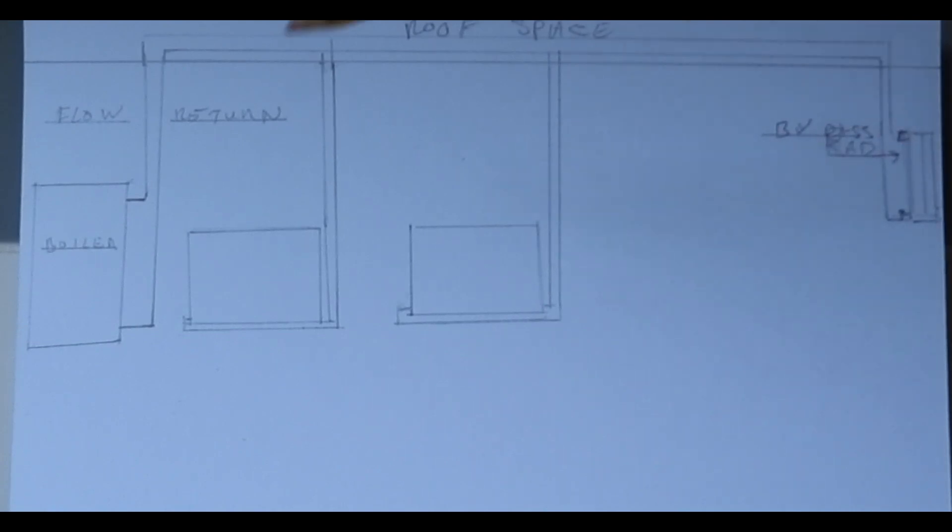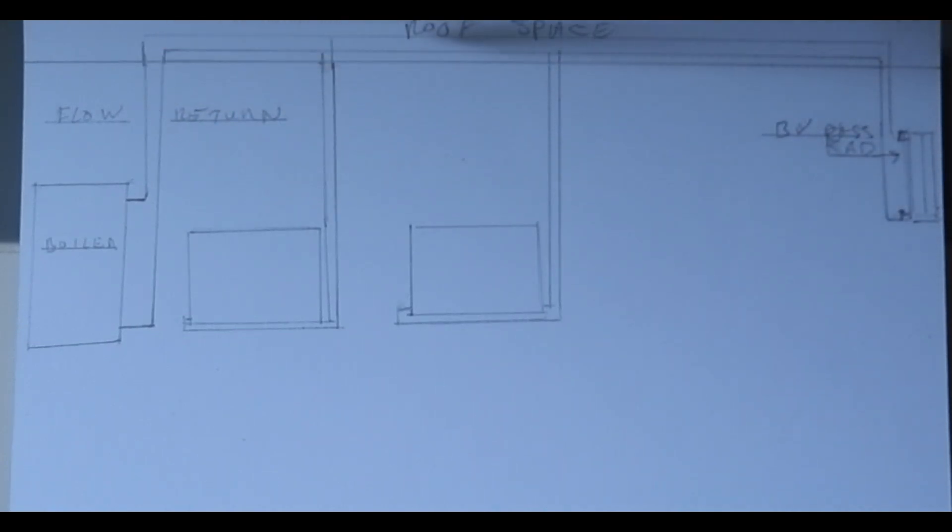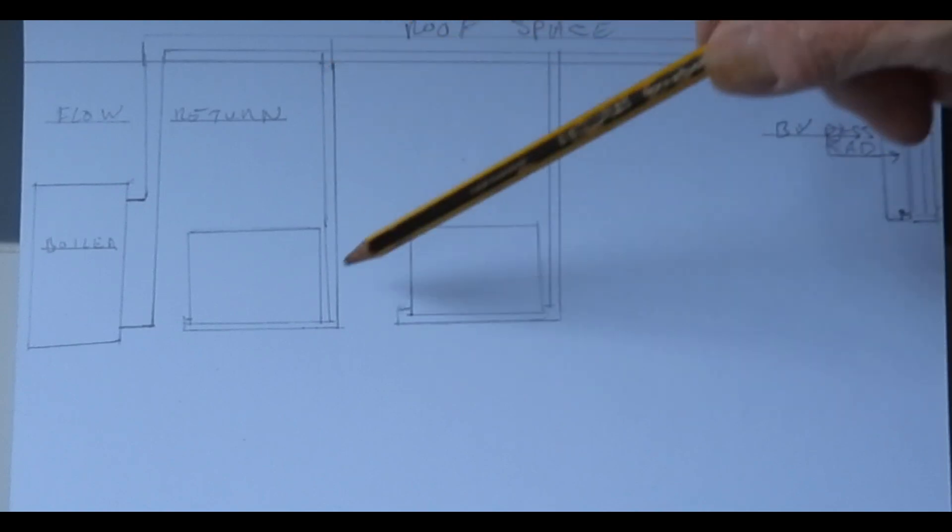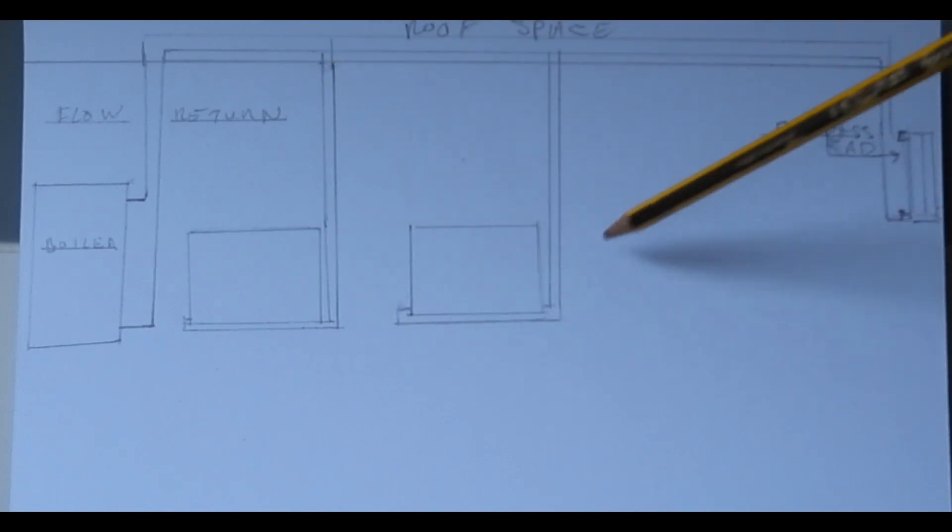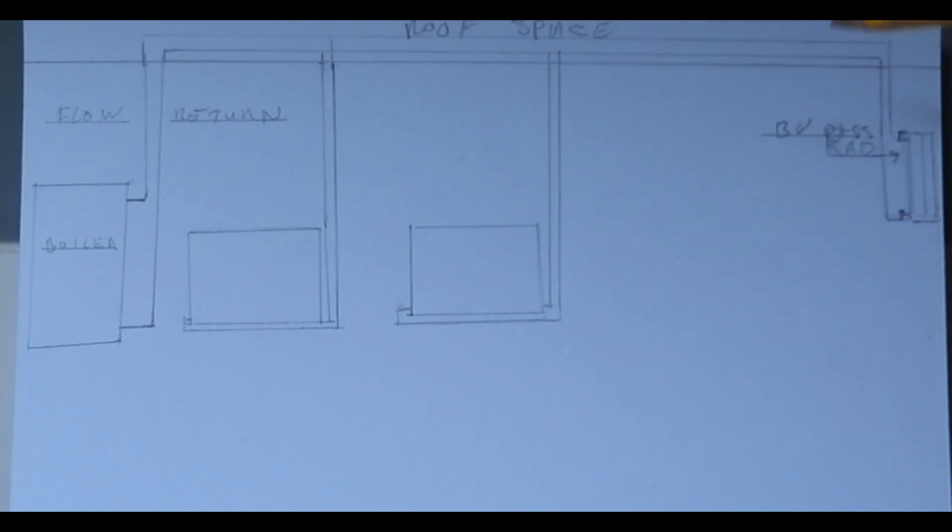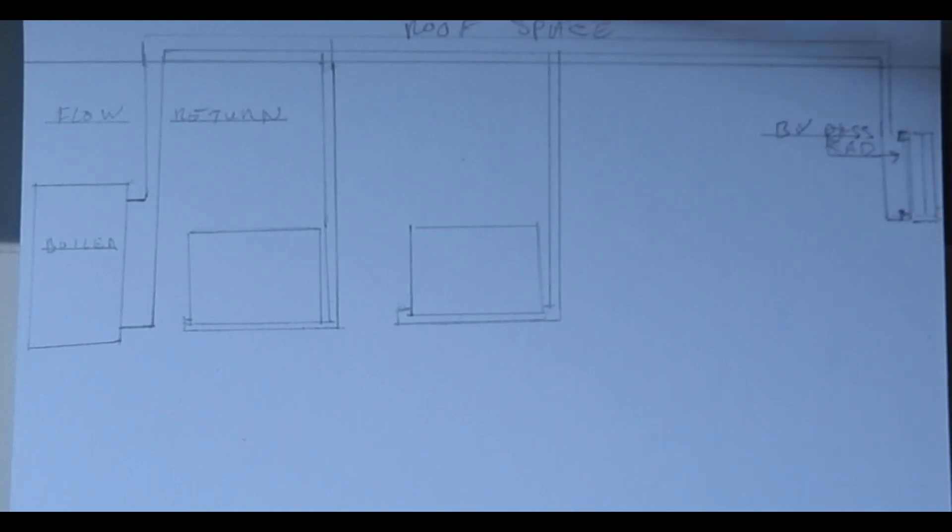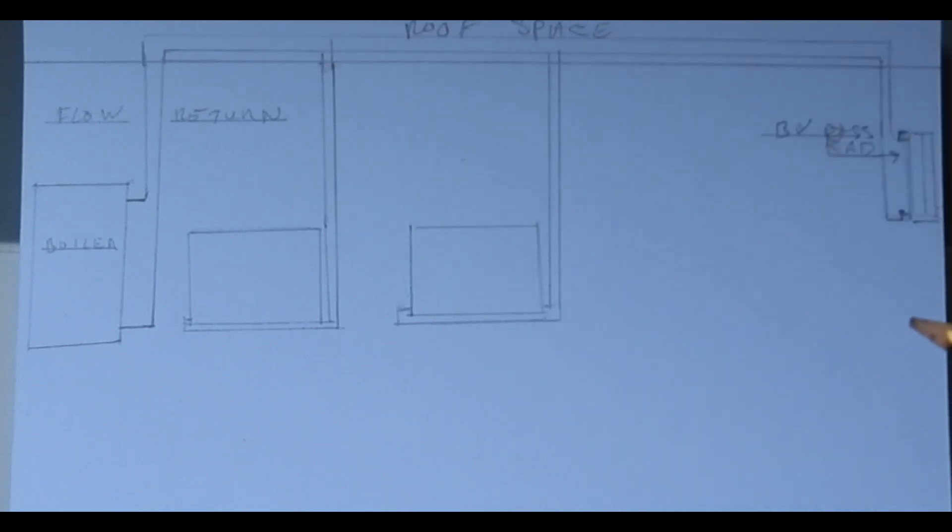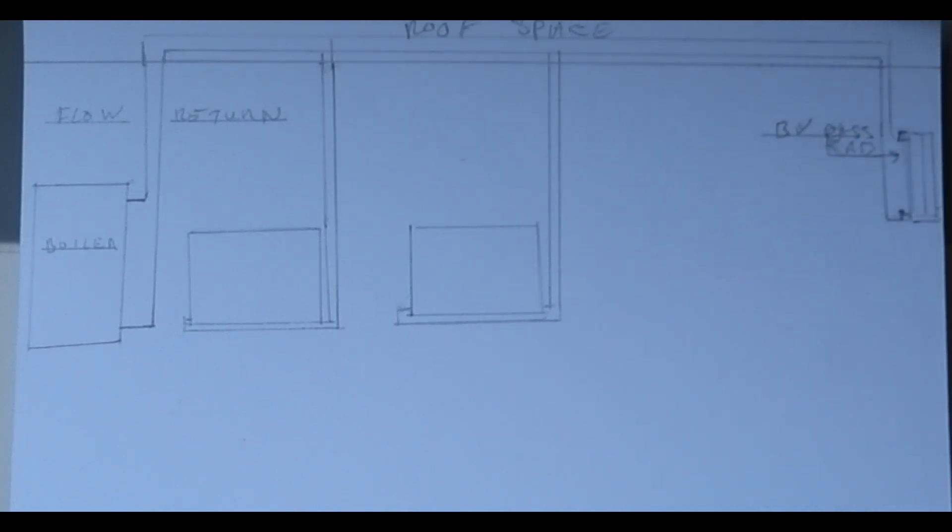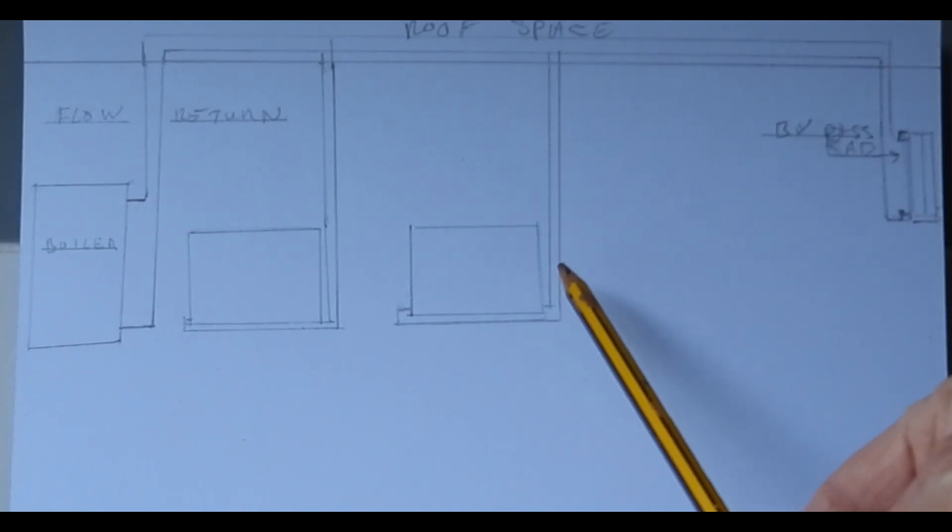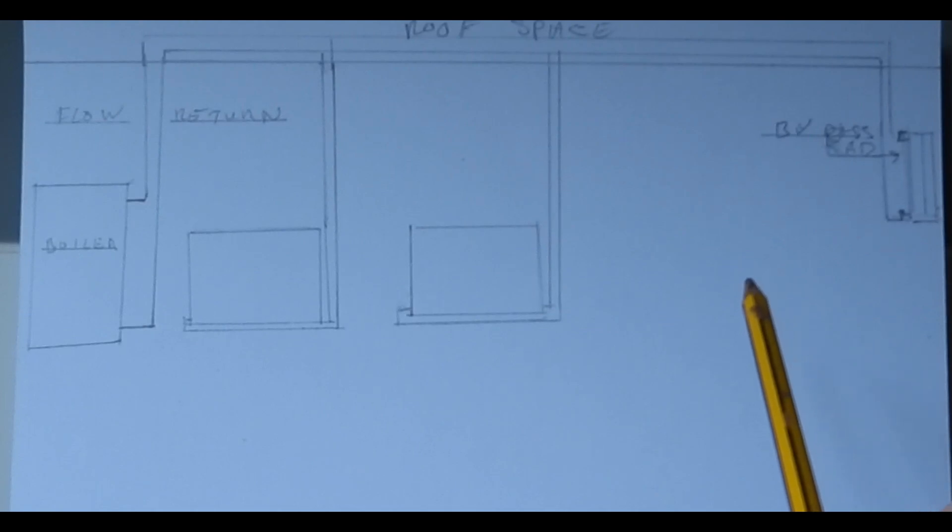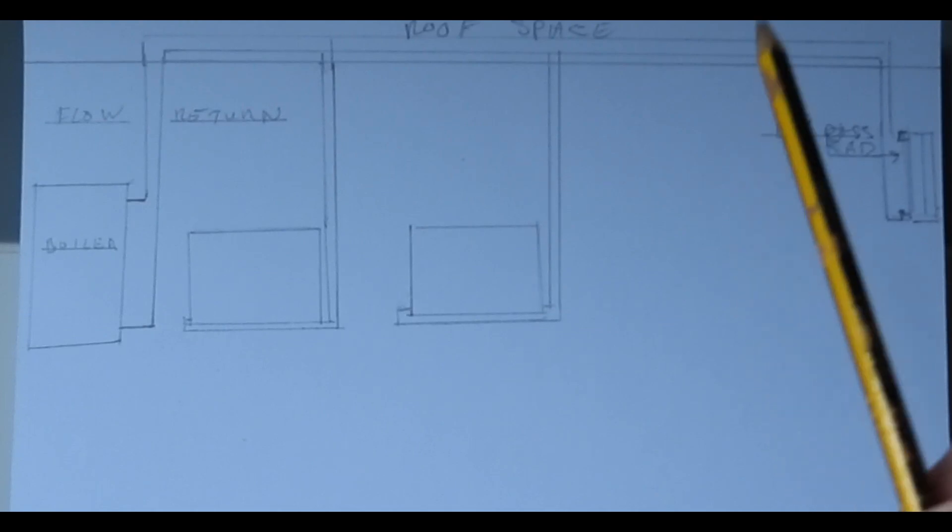So here's a typical system. The pipes are going up into the loft, running down, teeing down to the rad and coming back up again. I've only done two rads but it could be loads, as many as 10 or 11 rads. When it gets to the end, the circuit usually goes into a bypass rad, usually something like a towel rail, and then it goes back to the boiler. You can add rads on that drop, but I've been asked if you could tee off of one of these and just put an extra rad in a room.